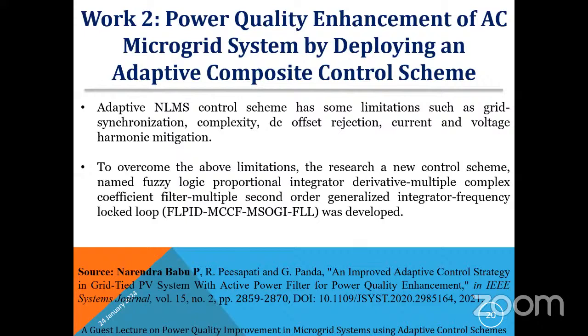So what is the DC offset here? If the mean amplitude of the grid currents is equal to 0, then your DC offset is equal to 0. If the DC offset is high, that means what? Your three phases do not maintain constant magnitudes. The magnitudes are different, so what will happen? The connected appliances will be destroyed. So we have to maintain all three phases at the same magnitude.